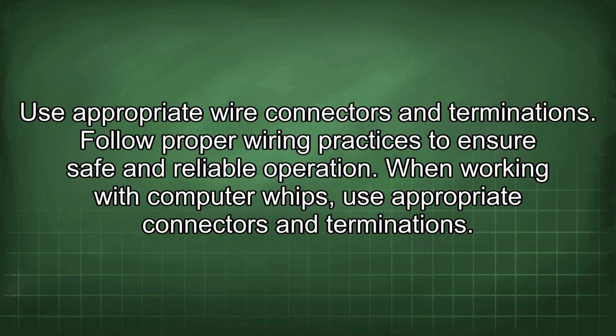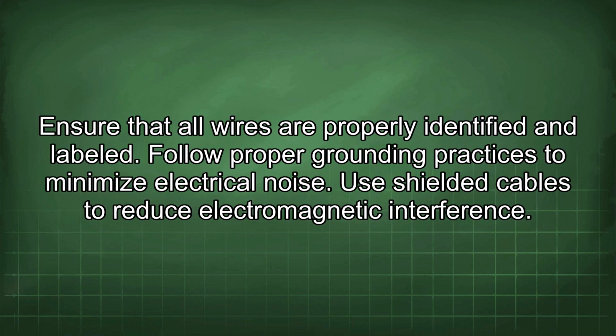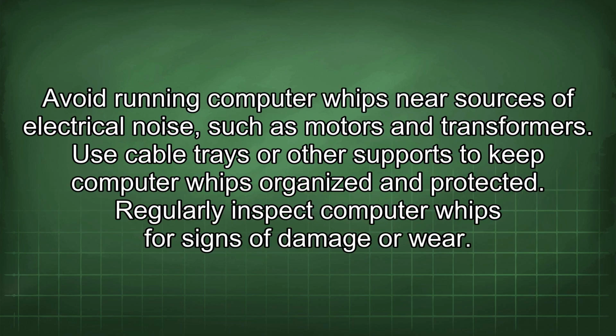When working with computer whips, use appropriate connectors and terminations. Ensure that all wires are properly identified and labeled. Follow proper grounding practices to minimize electrical noise. Use shielded cables to reduce electromagnetic interference. Avoid running computer whips near sources of electrical noise, such as motors and transformers. Use cable trays or other supports to keep computer whips organized and protected.